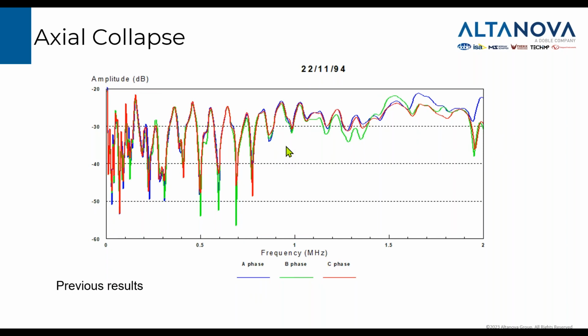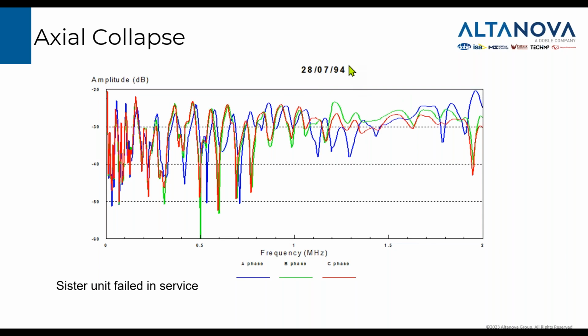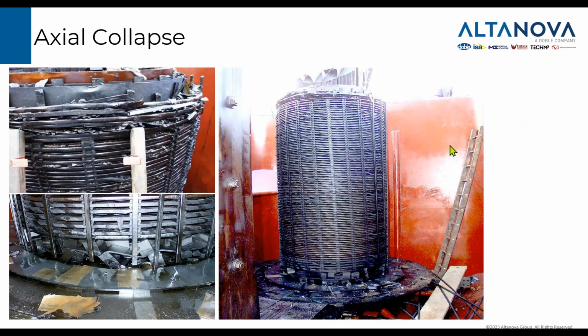So this was the previous result, and this was another transformer with which we already had experience before. Again, in 1994, a sister transformer failed, and it failed in similar ways. There was again this A phase shifted, but to a higher degree. So we had some supporting information, and this is what we found. The coil was crushed from top and from bottom. You can see the bottom blocking system is damaged, and the top supports were also damaged, and it's also visible on the leads. They collapsed, and the winding was a little bit twisted. So this was identified with SFRA.